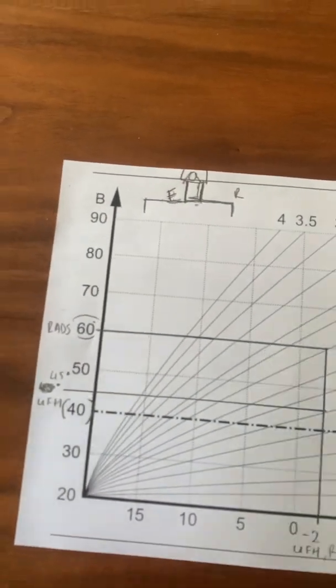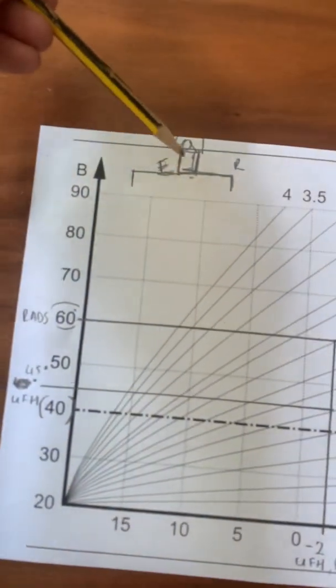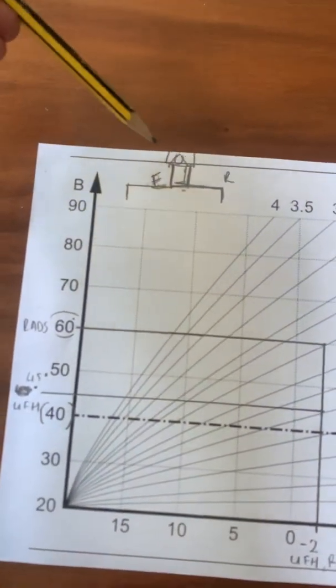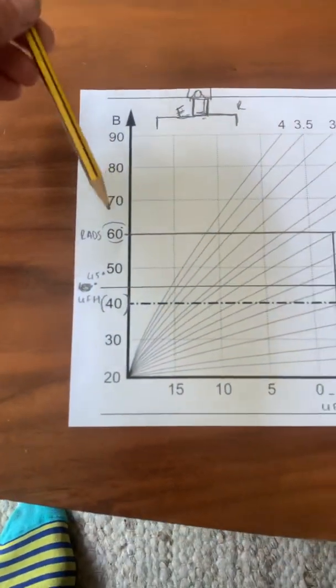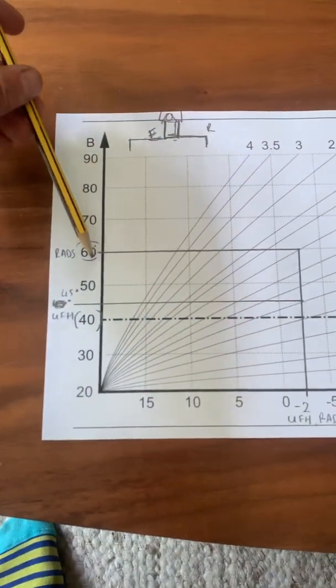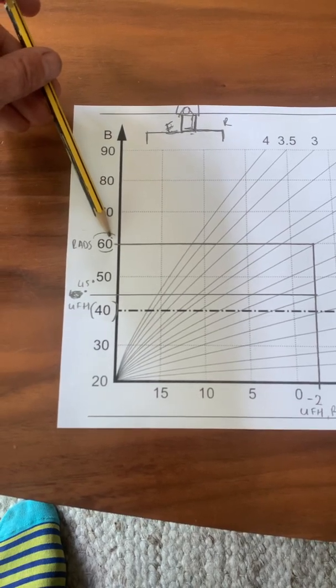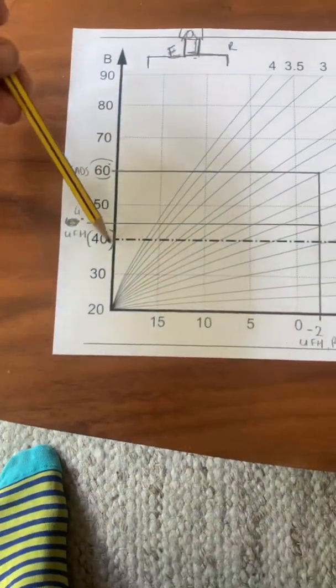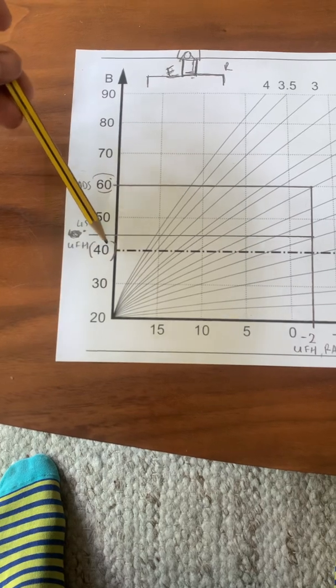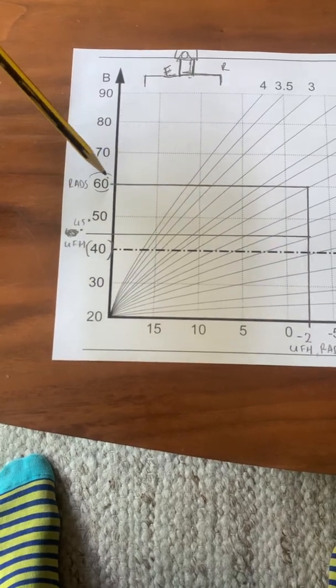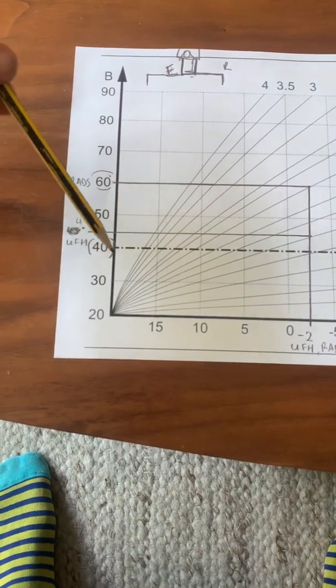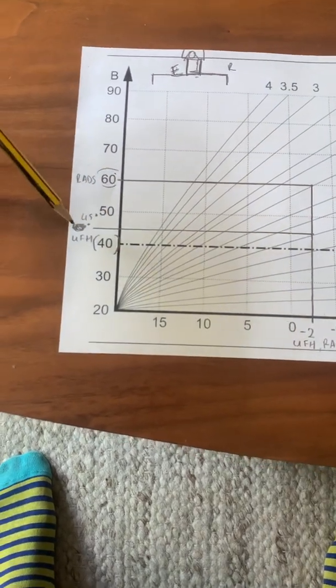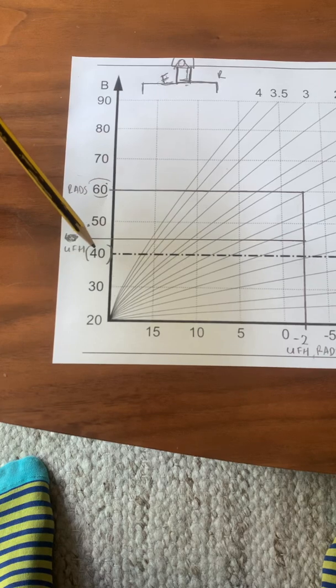So what we've got is our boiler running at 60 degrees, but our underfloor heating needs only 40 degrees. And that's what the mixer is doing: it's taking a certain amount of the 60 degrees and then it's cooling it with its own return water and cooling it down to 40 degrees by opening and closing the flow port or the return port.